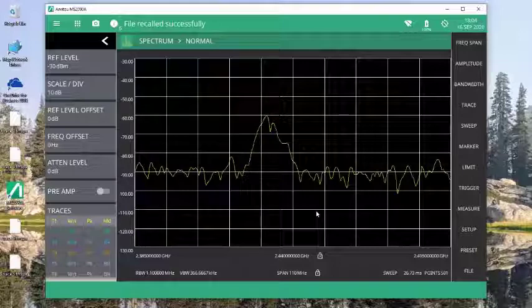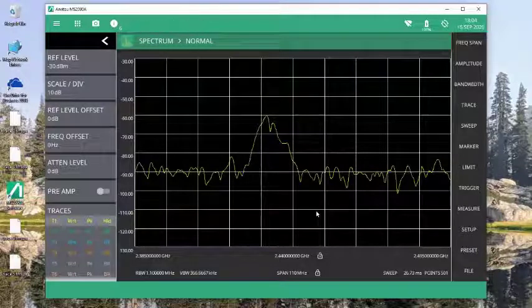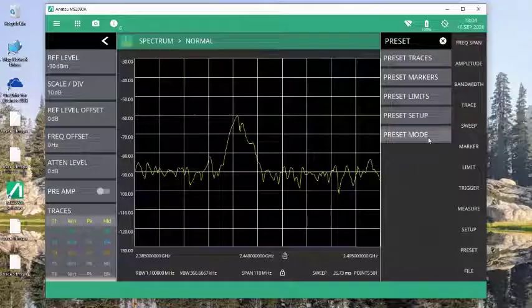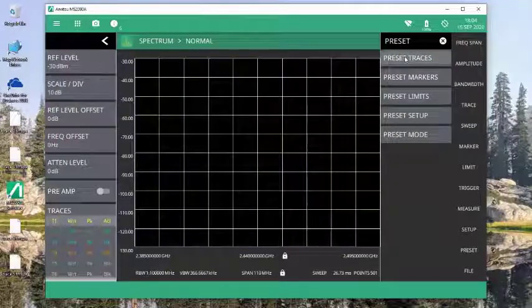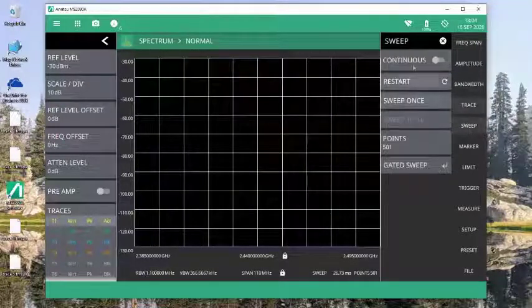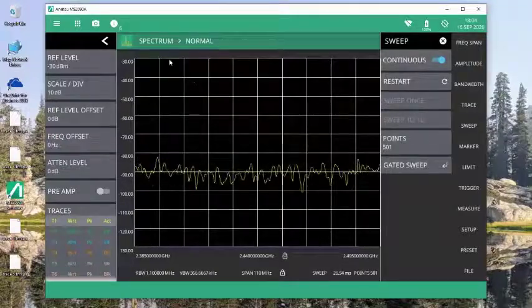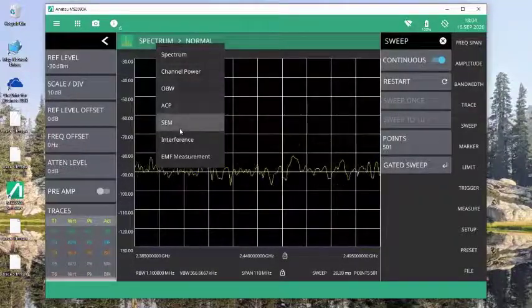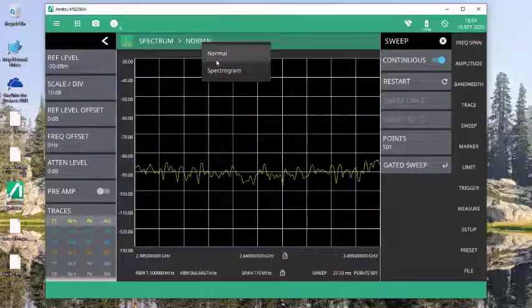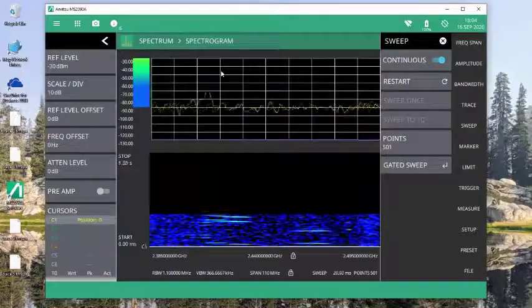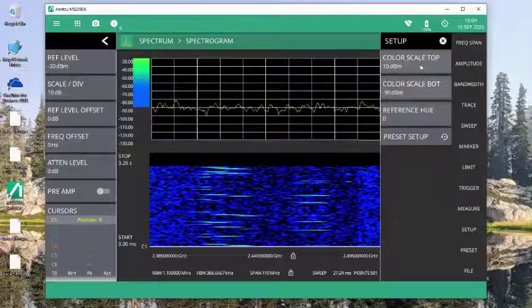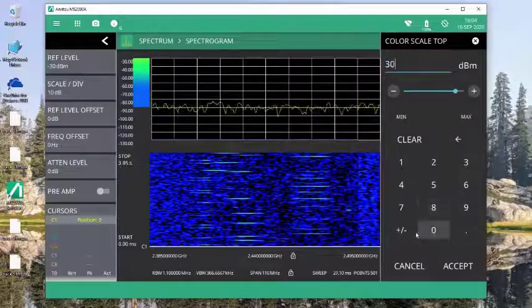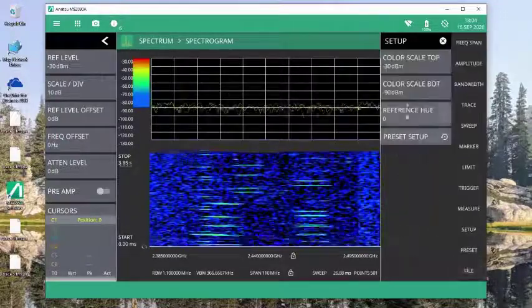Okay, so the feature also works extremely well in a spectrogram mode. So I'm going to preset my traces here and go back to sweeping. And I'm going to look at this information now in spectrogram. So change the view to spectrogram. And I'm going to set this up a little bit lower so I can see some more resolution on the data.